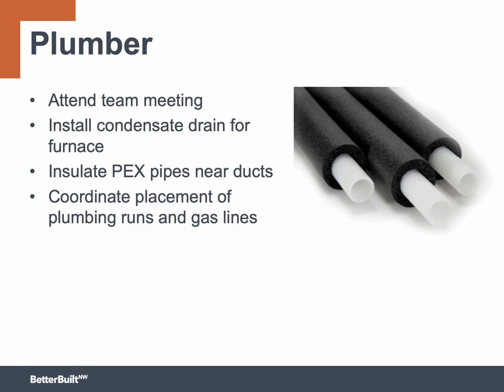It depends on the particular project whether the plumber needs to be involved in the team meeting. The plumber is going to need to know where to put the condensate drain for the furnace, and in some cases, when PEX pipe is installed near a heating duct, it must be insulated. So that may be something that's not often encountered in a conventional project. Be sure to coordinate the placement of plumbing runs, especially gas lines, with the HVAC contractor.